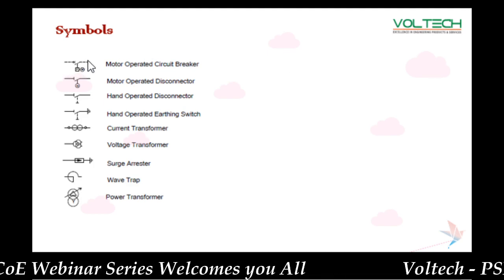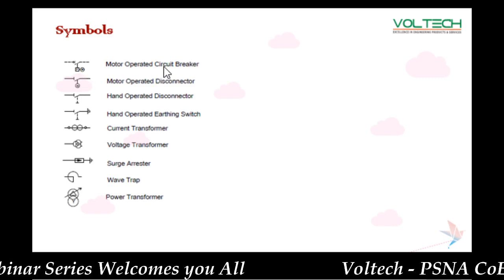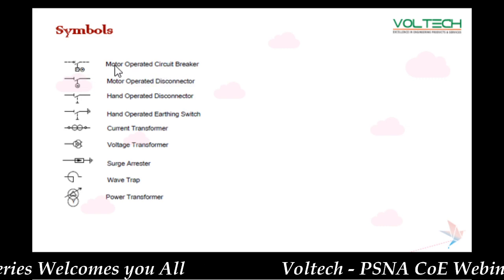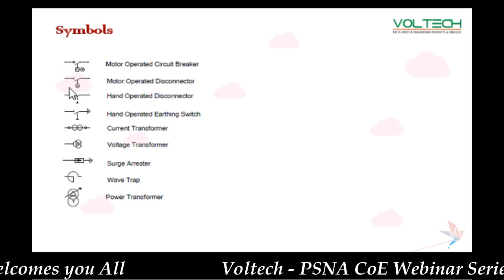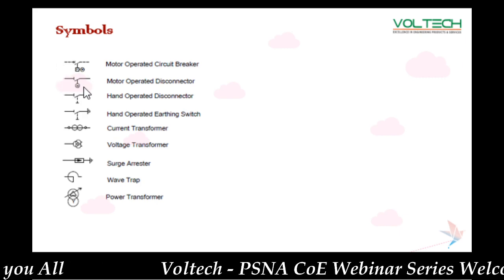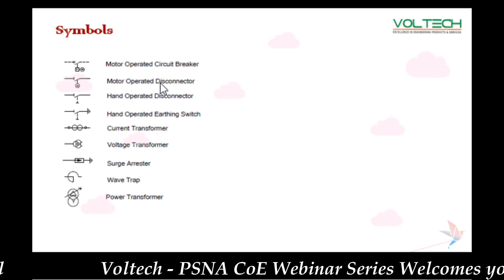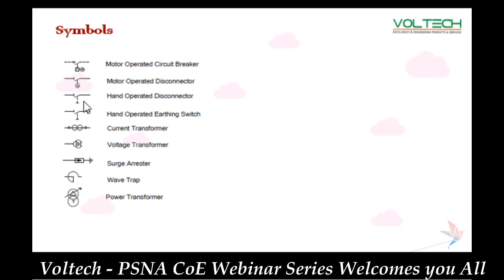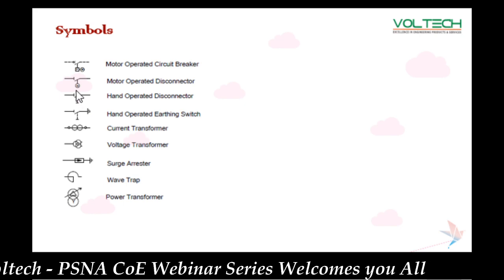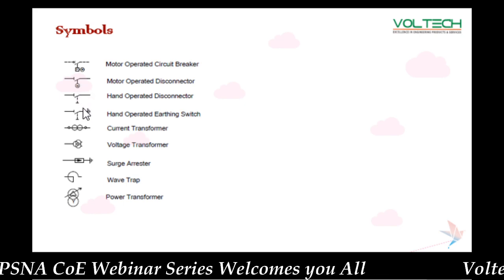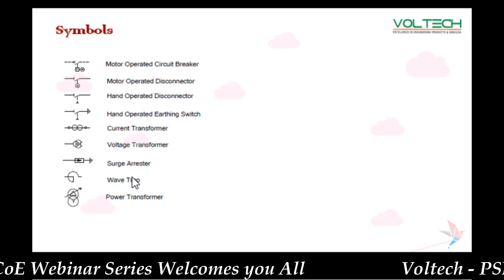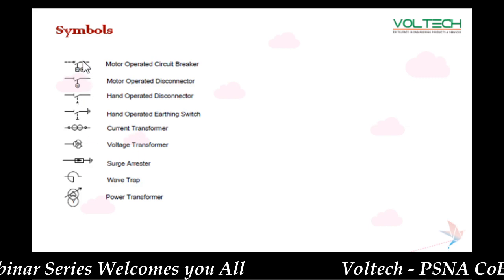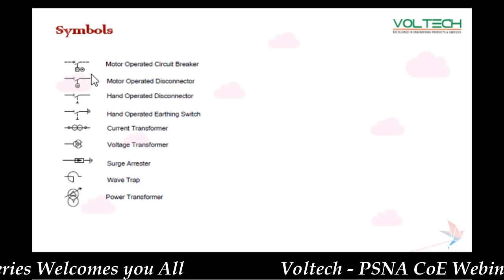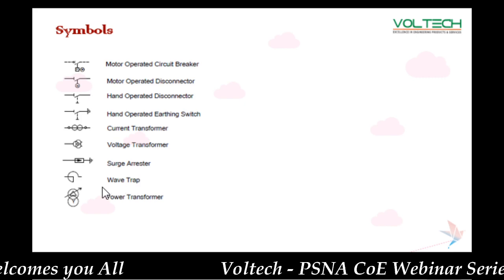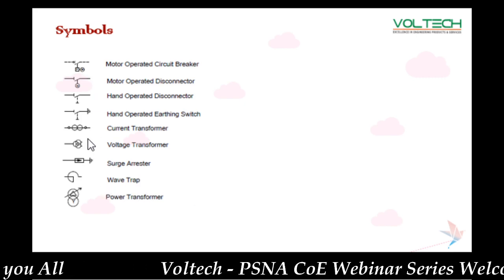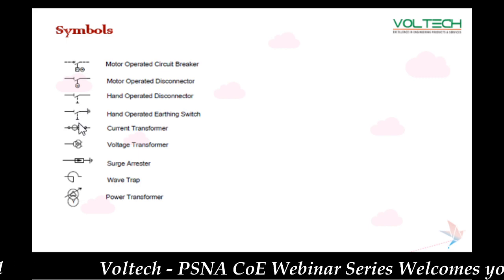This is the motorized operator — the motorized operation of a circuit breaker, where the circuit breaker is operated by a motor — and this is the motor-operated disconnector, which we can call a disconnector or isolator. But here this one is hand operated. The symbols should be clear, because in further days we are going to talk about the SLD or any drawing using these symbols, and we'll read the scheme with these symbols only.